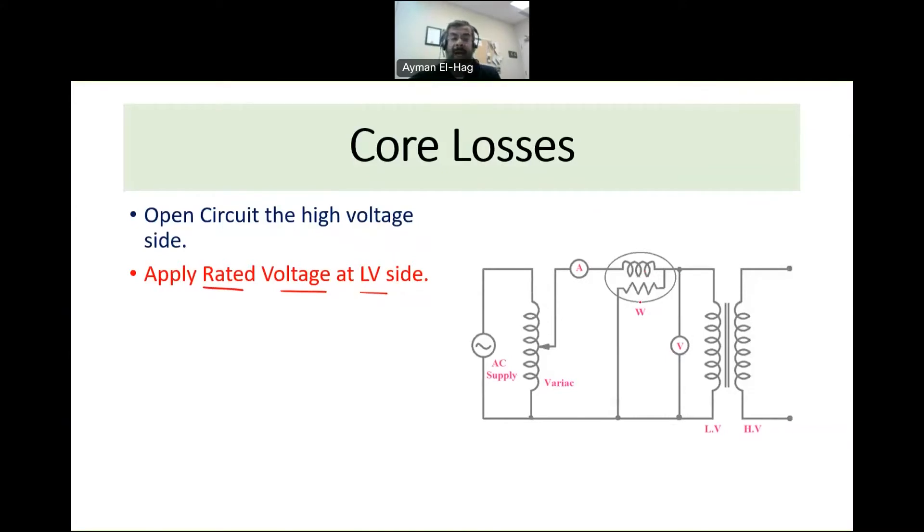This power loss is actually approximated to the no-load loss because there is a little bit of winding loss. As you can see here from this configuration, this loss is dependent on the voltage - it is a function of the voltage, because we have very small current we call it the no-load current or the excitation current. This is usually 3 to 5 percent of the rated current, so there will be some losses in the winding but it's very negligible compared to the core loss.